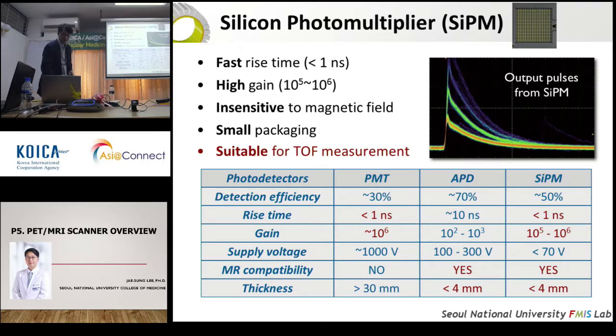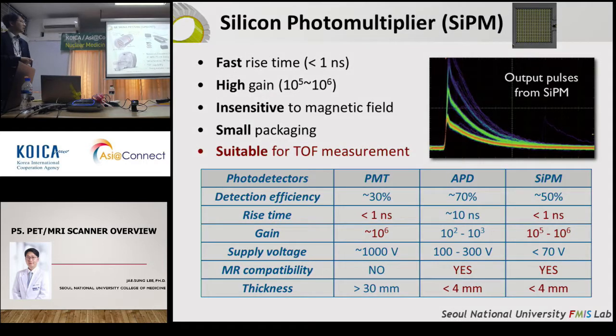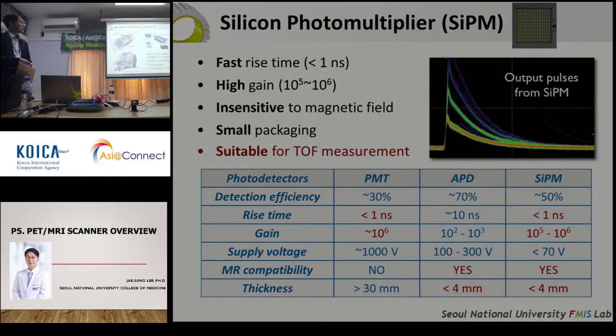I mean the conventional photomultiplier tube, the avalanche photodiode, and the silicon PM. As I told you, there's a difference in the gain, the signal amplification, between the PMT and the avalanche photodiode. But the silicon PM has quite an equivalent gain to the photomultiplier tube. The silicon PM is also comparable to the diode in compactness. So that is why, as I told you, we have worked on silicon PM based PET systems.